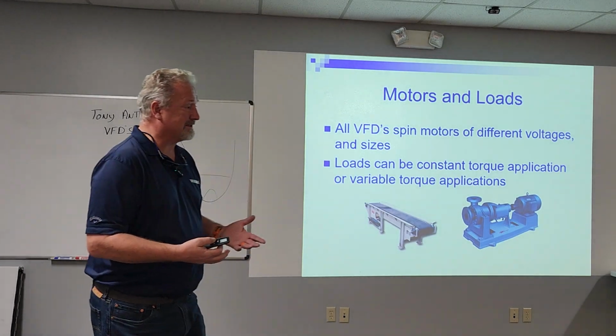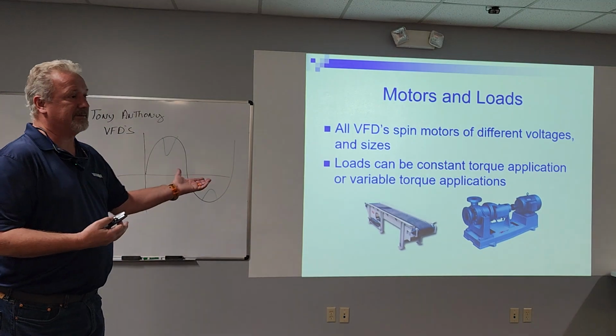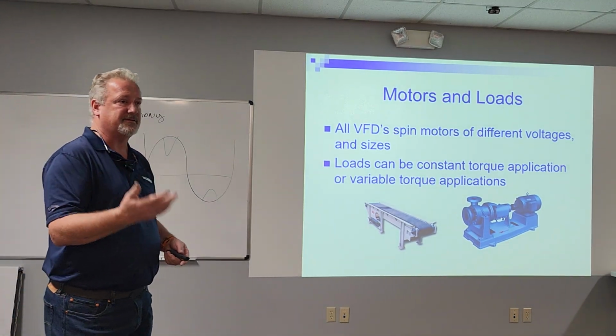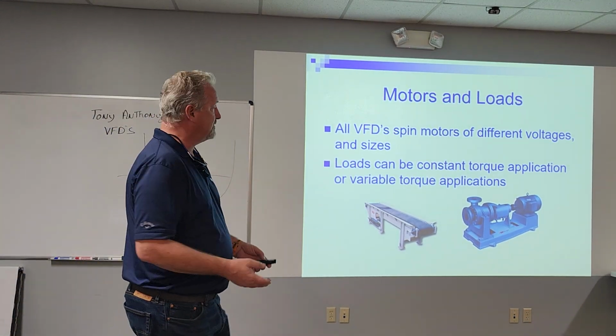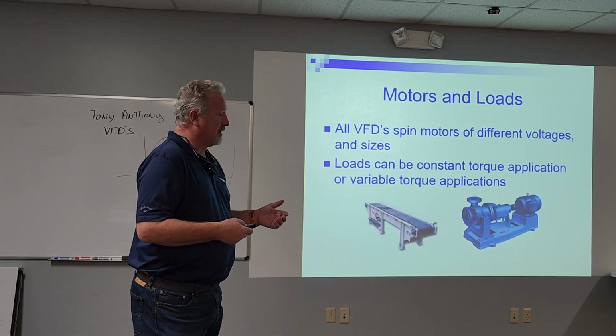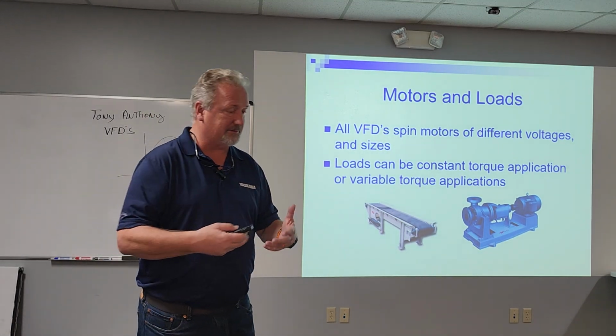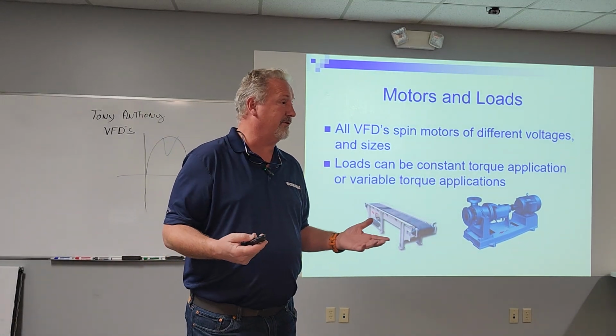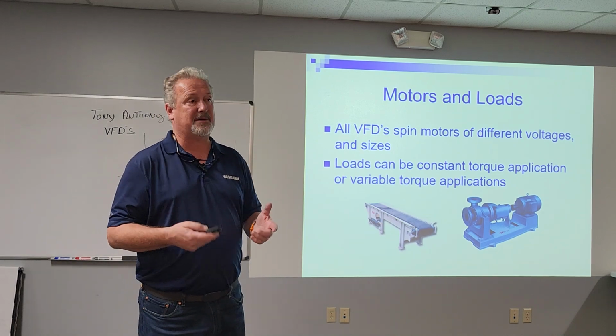So really on the output side, that's the most common things we might use. There's some other things that could come up in different scenarios. If they do, you're talking to some engineers. So we've got load reactors and we've got output disconnects. That's pretty much all we're ever going to see between the drive and the motor in most applications.